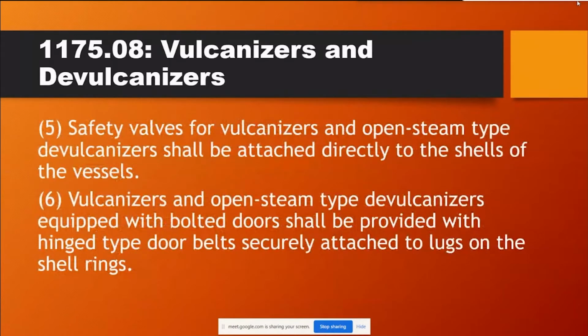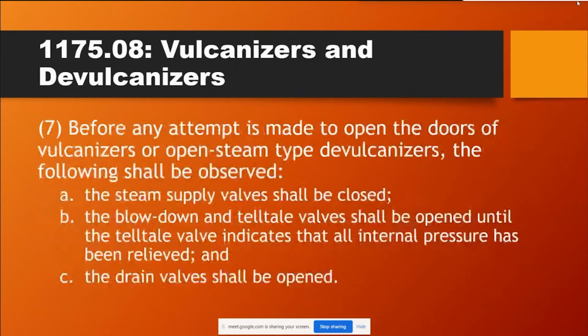Safety valves for vulcanizers and open steam type devulcanizers shall be attached directly to the shells of the vessels. Vulcanizers and open steam type devulcanizers equipped with bolted doors shall be provided with hinge type door bolts securely attached to lugs on the shell rings. Before any attempt is made to open the doors of vulcanizers or open steam type devulcanizers, the following shall be observed. The steam supply valves shall be closed. The blowdown and telltale valves shall be open until the telltale valve indicates that all internal pressure has been relieved, and the drain valves shall be open.